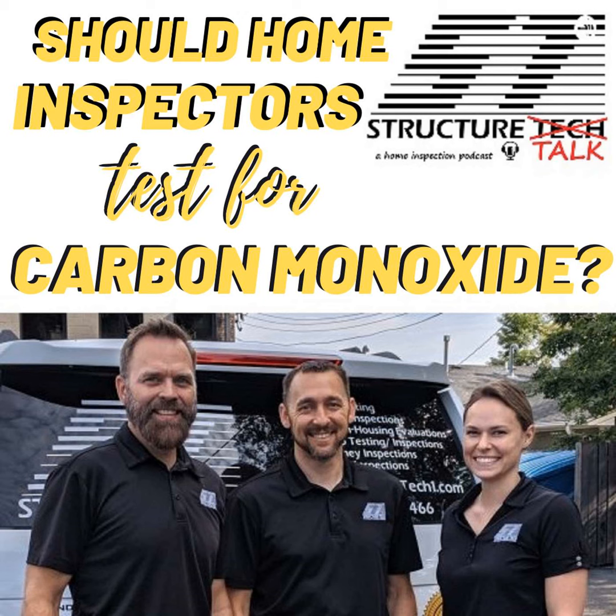All right. So Tess, what about if it's got a draft inducer? Where do you test there? For draft induced furnaces, you want to test that flue gas in the flue about 6 inches above the hood. And ideally, I think no more than 18 inches.